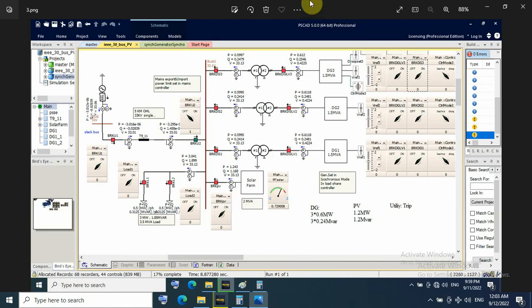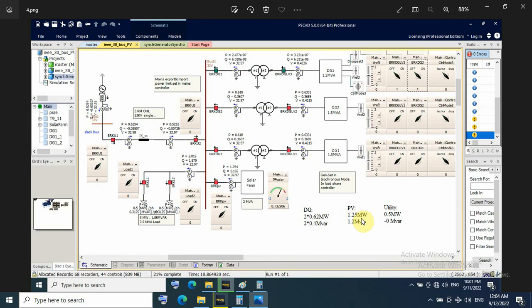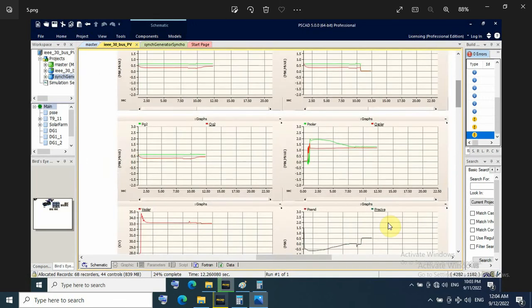Here in this case to show, so I have 2 DG, each DG generates 0.6 megawatt, and PV generates 1.25. And utility I will take 0.5 megawatt as active power import from utility and zero megavar at unity power factor.